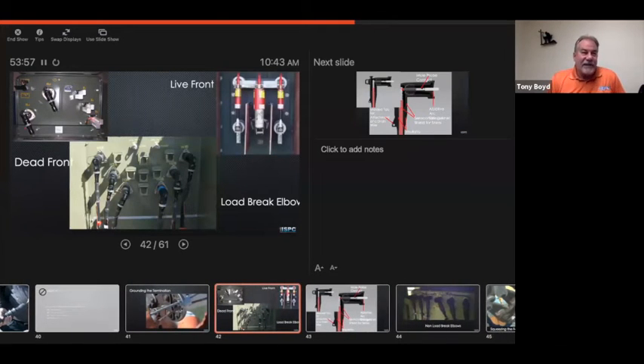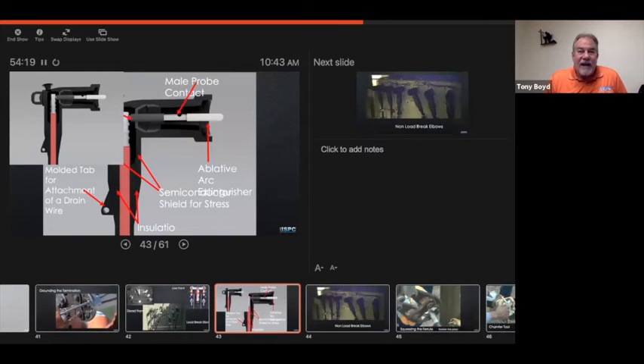3 different types of transformers. You got your dead front, top left, your live front, top right, and then load break elbows. If you notice these load break elbows, they all have a white stripe on them. So that indicates to us that they're a load break elbow. If they do not have a white stripe, it could be that they do not have the ablative tip. So on the right-hand side, you see the ablative arc extinguisher tip, and that's what makes it load break. So inside, and thanks to Jerry for these 3D models, we have the transformer bushing, which comes all the way out to here, and it makes a little locking right here. There's actually some teeth on the male probe contact. So when you pull the elbow out of the bushing, this ablative tip suppresses the arc.